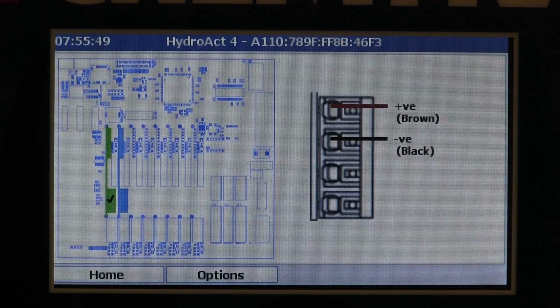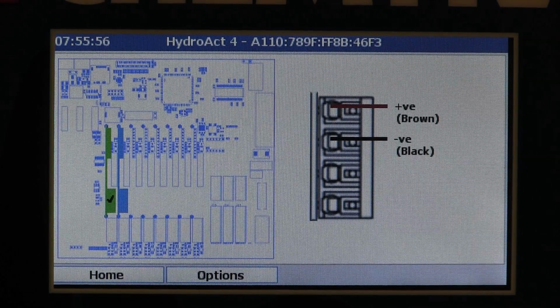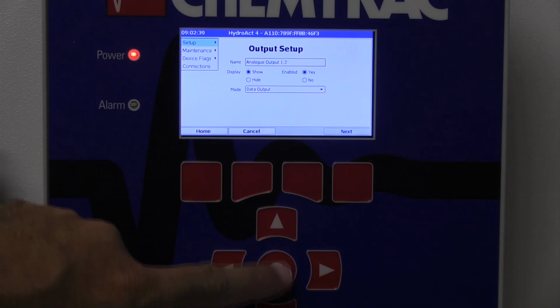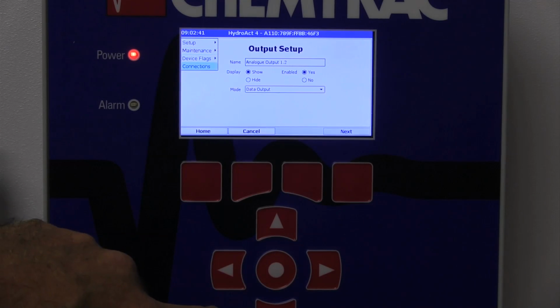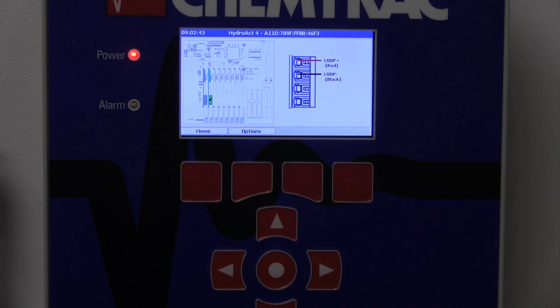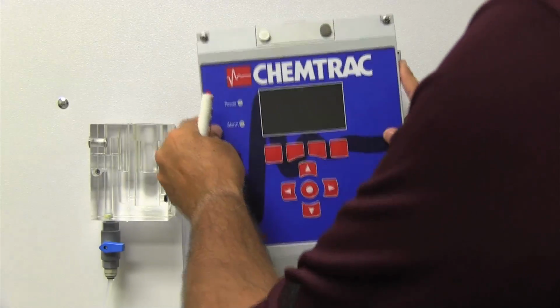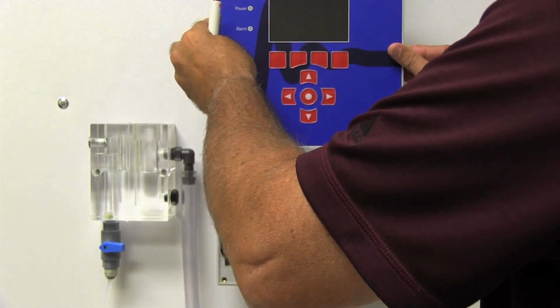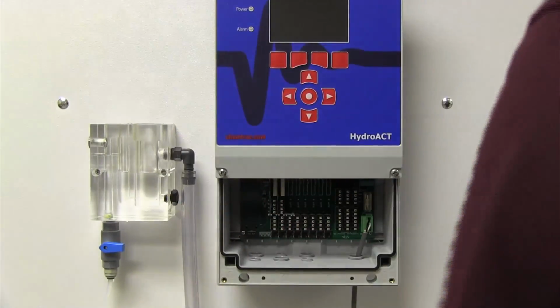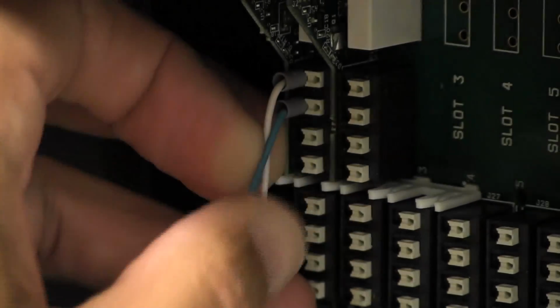The Hydroact Analyzer offers on-screen wiring connection diagrams for the sensor as well as for various I/O options. These diagrams can be accessed through the menu options, including analog outputs, relays, and digital communication. The faceplate can be moved to a raised position to reveal the connection terminals and allow for easy wiring access. The probe connections are made using simple press-to-open connectors.